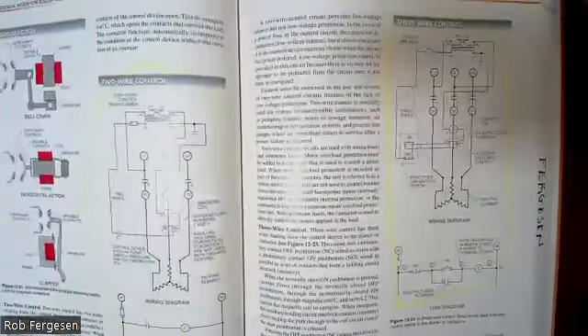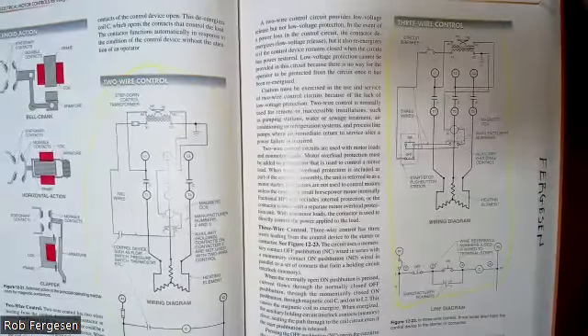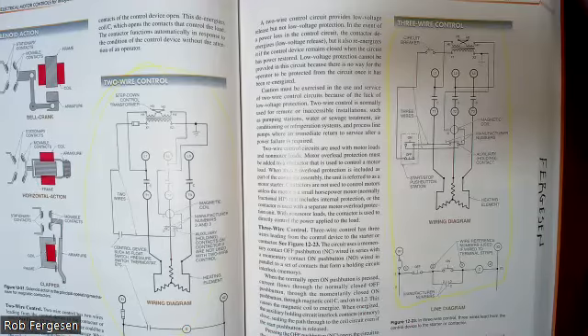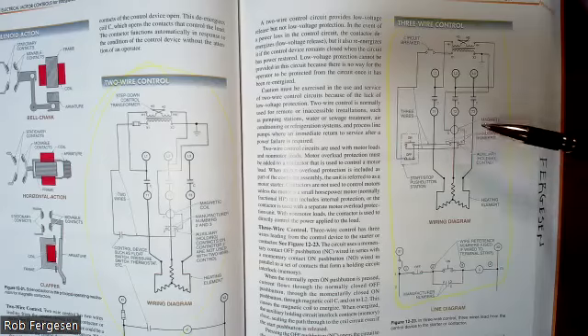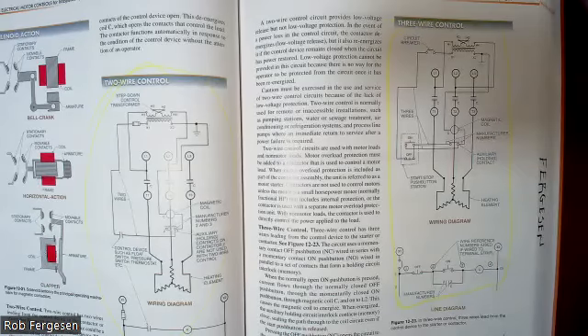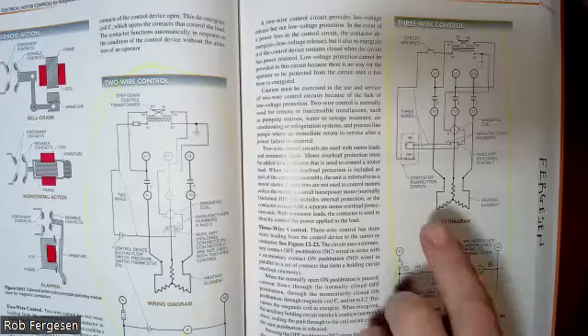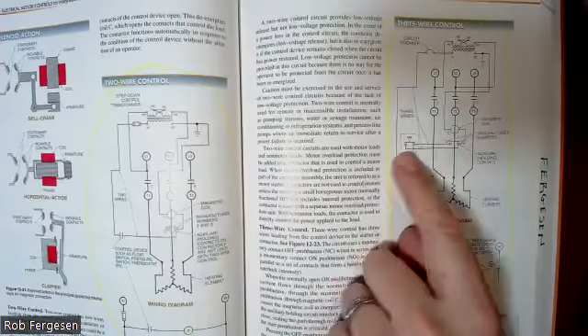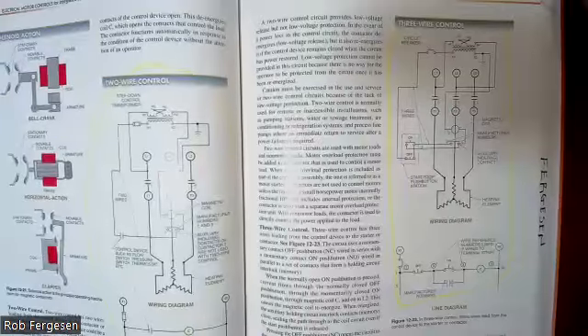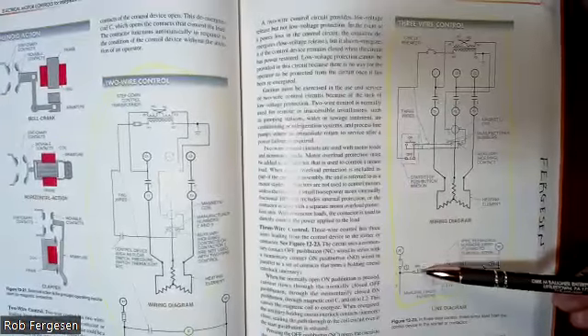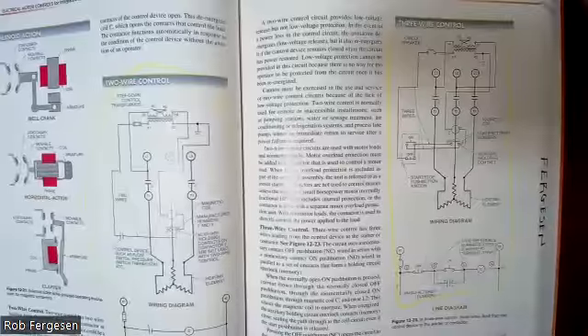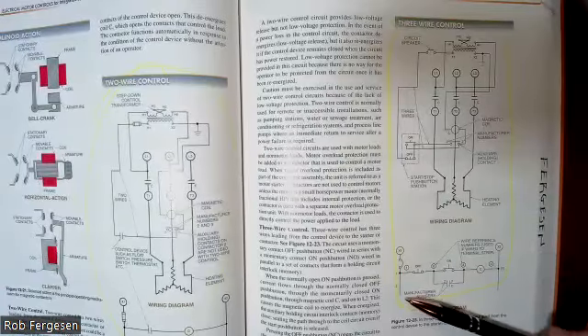On page 249, we have the same thing, more typical for a 3-wire control. 3-wire control means you need slightly more complex control power, and you need an auxiliary contact on your contactor. That auxiliary contact means that I can use a push button and it will latch on the power, right? And then I have an off button that unlatches the power. So this is a very, very important configuration to understand.